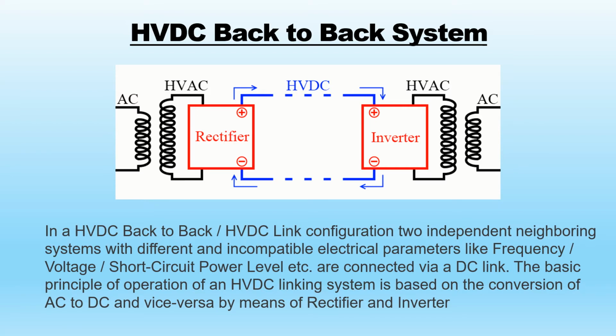The basic principle of operation of an HVDC link system is based on the conversion of AC to DC and vice versa by means of rectifier and inverter, as you can see in the diagram. The process involved in this system is simple. Power from two or more neighboring systems is first converted into DC with the help of power rectifier system and summed up. After summing, the resulting power is again converted to AC with the help of power inverter and supplied to different grids.